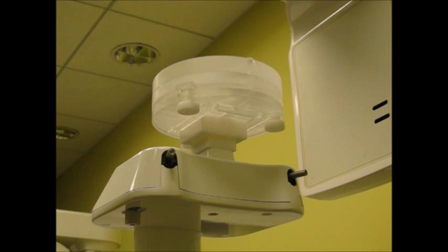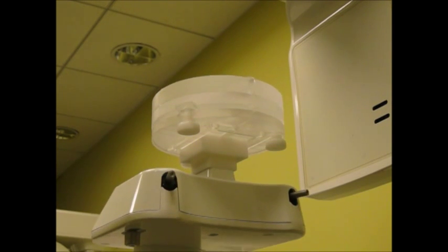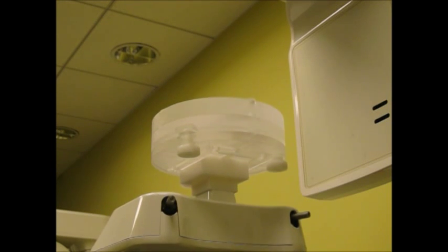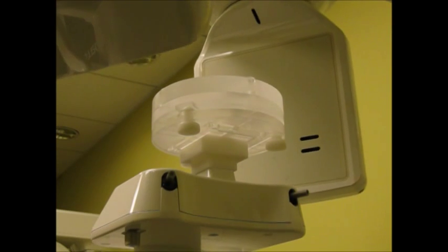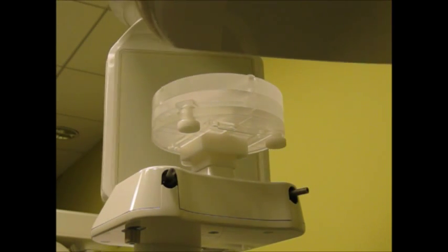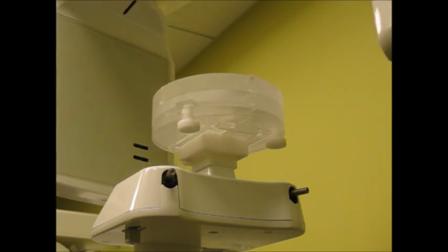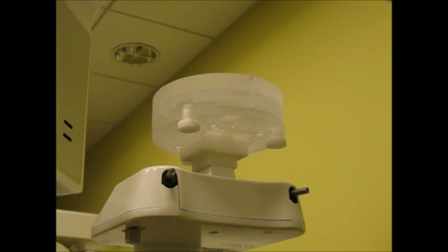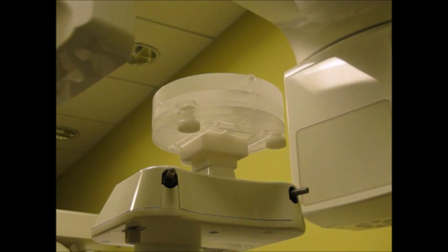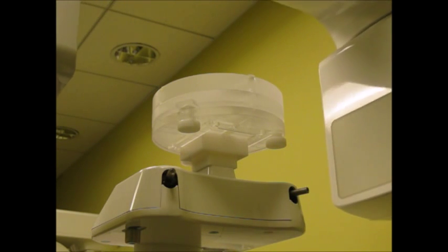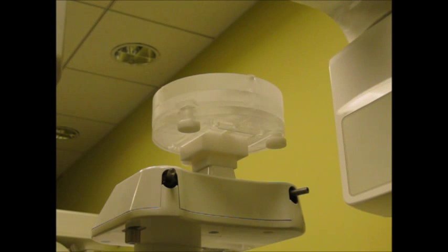Remember that in our last test we had the CT number phantom on top. As we initialize the machine for the next CT scan, the machine will move. Once the machine stops, we will remove that top CT number phantom, and we will place a uniformity test phantom instead.